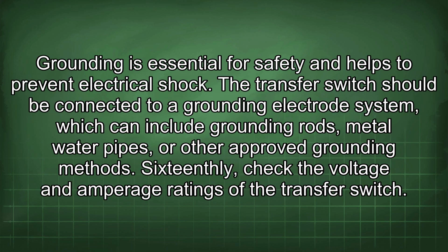15thly, ensure that the transfer switch is properly grounded. Grounding is essential for safety and helps to prevent electrical shock. The transfer switch should be connected to a grounding electrode system, which can include grounding rods, metal water pipes, or other approved grounding methods.